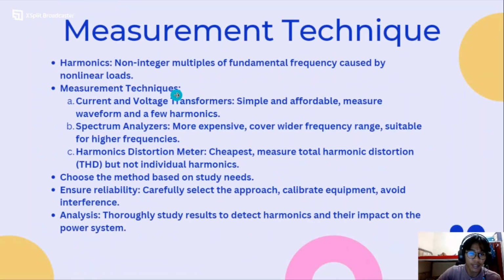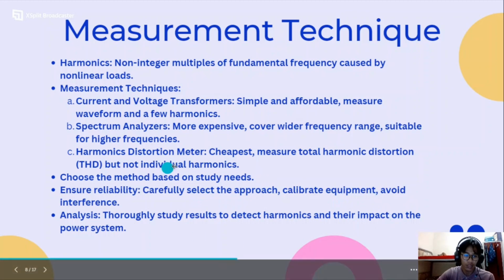For the measurement technique, we can use current and voltage transformers. It is simple and affordable, and measures waveform and a few harmonics. Next is the spectrum analyzer. It is more expensive, but it can cover a wider frequency range and is suitable for higher frequencies. And lastly, the harmonic distortion meter. It is the cheapest. It can measure total harmonic distortion, but not individual harmonics. We need to choose the method based on the study needs. To ensure reliability, we need to carefully select the approach, calibrate the equipment, and avoid interference.